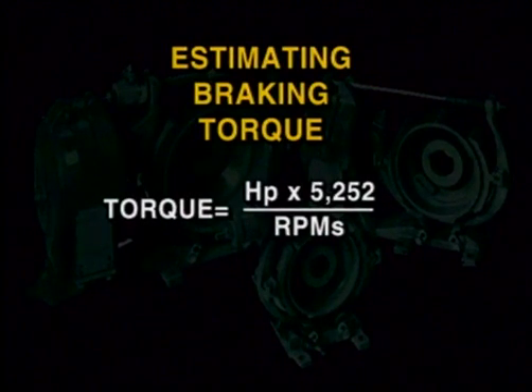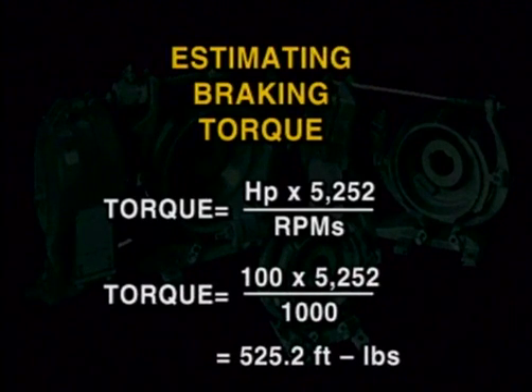To obtain this value, you can use the equation of torque equal to the horsepower of the motor times the constant 5,252 divided by the speed of the RPMs at which the motor is operating. The value of the torque will be in foot-pounds, and the brake's torque should be equal to or greater than this value. For example, a 100-horsepower motor running at 1,000 RPMs will need a brake of at least 525.2 foot-pounds.